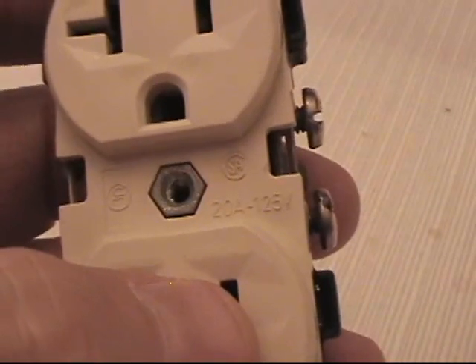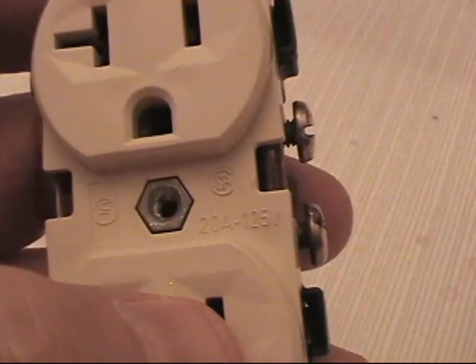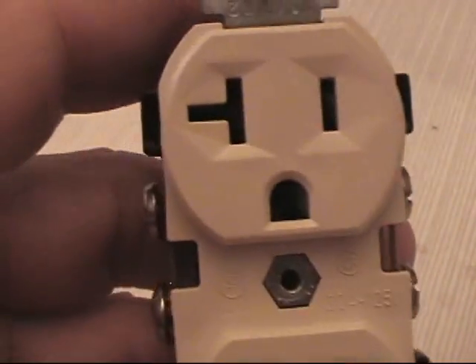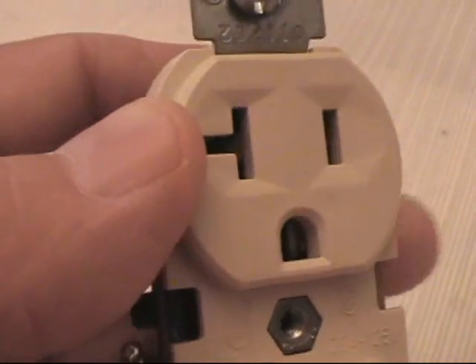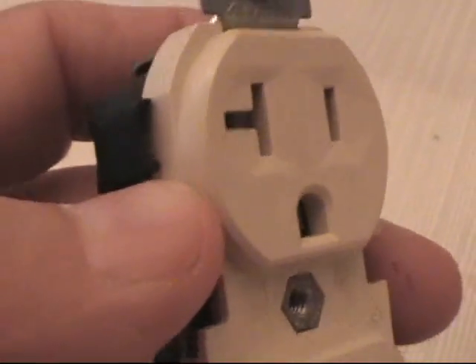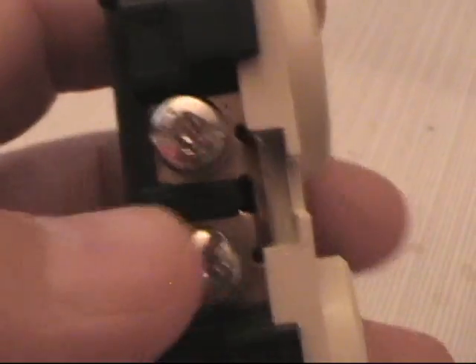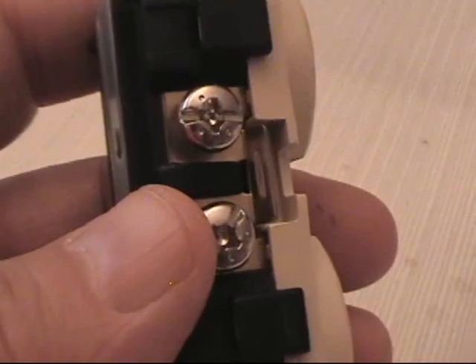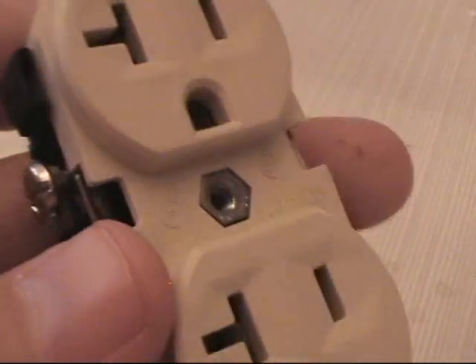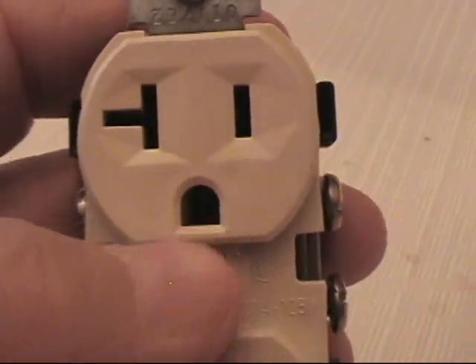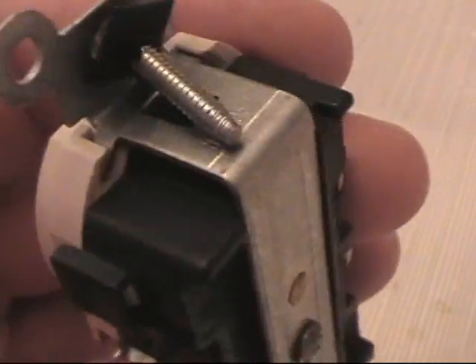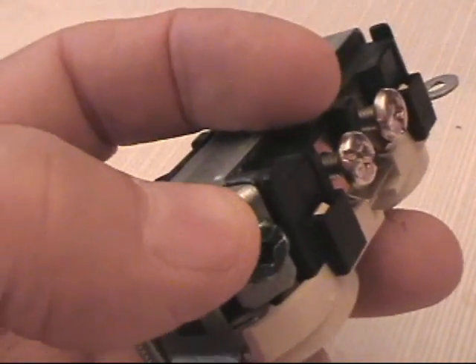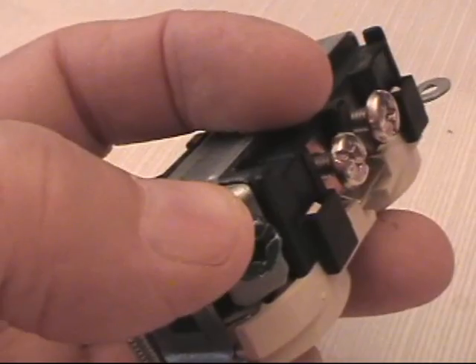The black wire in house wiring is always a hot wire. This side is the neutral side, or the ground, most grounded side, your return circuit. This is connected to the silver screws. That's where your white wire will attach. This, of course, is your ground prong. That is connected to this green ground screw right here. That is where your ground wire, your bare ground wire, would connect.